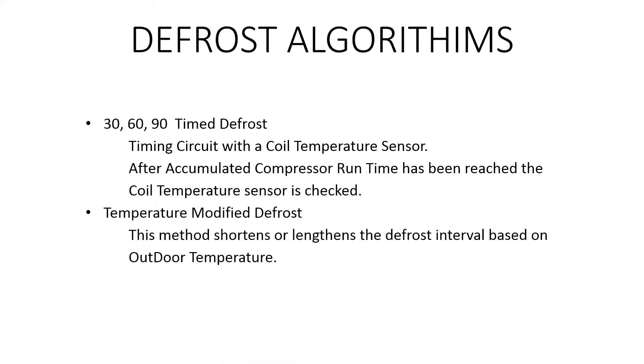The second defrost algorithm is the temperature-modified defrost. This method shortens or lengthens the defrost interval based on outdoor temperature.